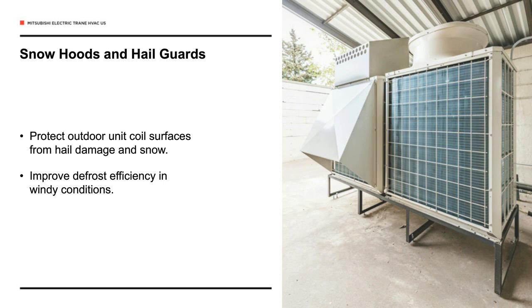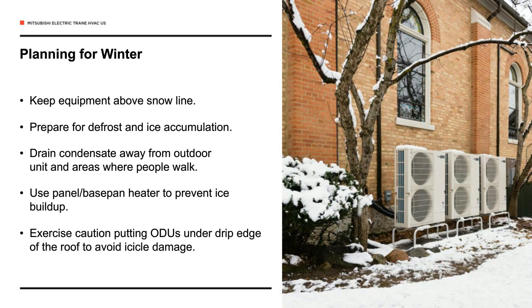And then in winter, you get those icicles that can be 2 feet long and 2 inches in diameter. And then in the spring, they break off and can come down through the condenser fan and destroy the condenser fan. The snow hood would prevent that. So planning for winter, as I said, keep equipment above the snow line. Think about defrost, where that water goes as it melts during the defrost cycle. Drain it away from sensitive areas where there could be slip hazards.